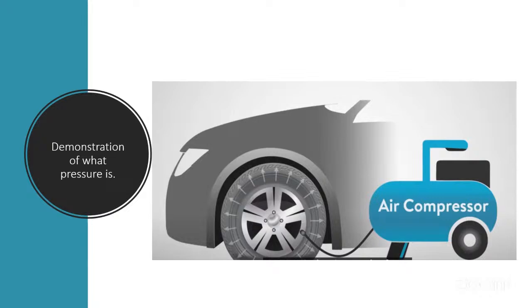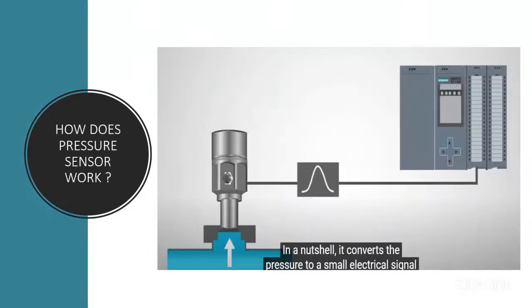So, how does a pressure sensor really work? Look at this next slide. You can see, in a nutshell, that it converts the pressure to a small electrical signal, which is transmitted to the PLC via the input card of the controller. And for this same purpose, it is also called the transmitter. The two basic types of signal used during the transmission are 4 to 20 milliamps or 0 to 5 volts, depending.